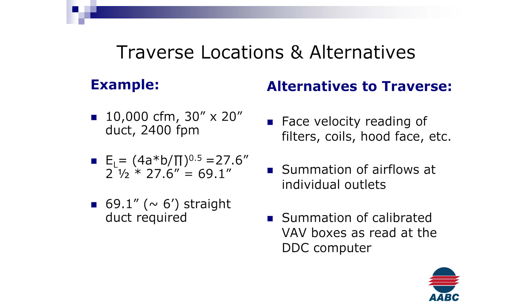Here's just some math and some alternatives to traversing: face velocity readings of the filters, coil, possibly the hood face. We can also, if we have to, use a summation of the outlets. But again, that's taking into consideration all the loss in the system. So you have to know you're moving more air back at the fan than what's actually coming at the summation of the outlets. And then, what is the summation of the calibrated VAV boxes?